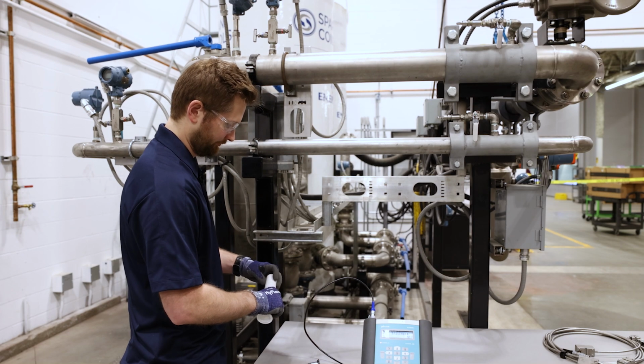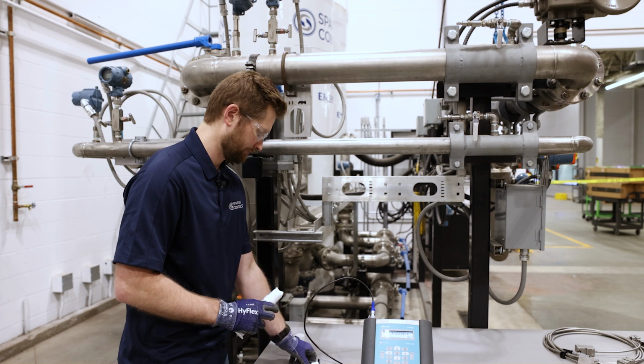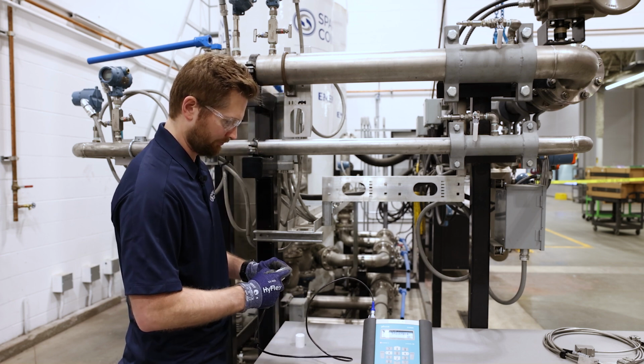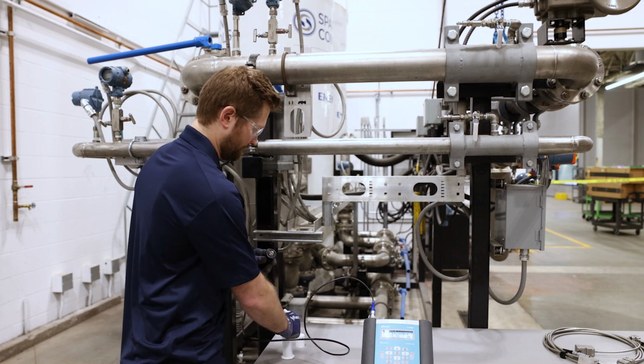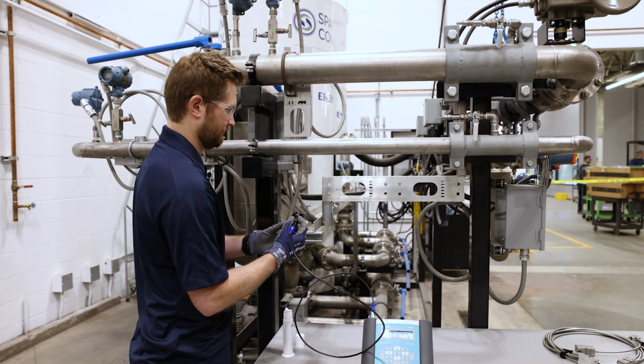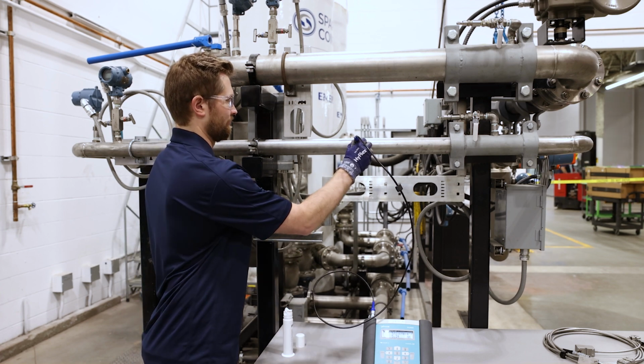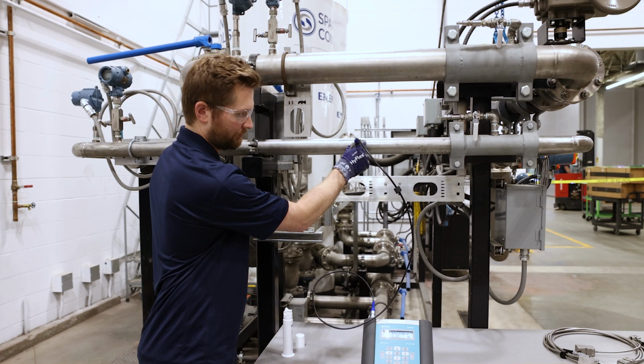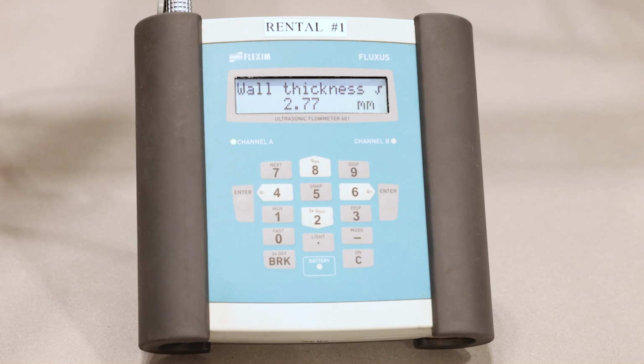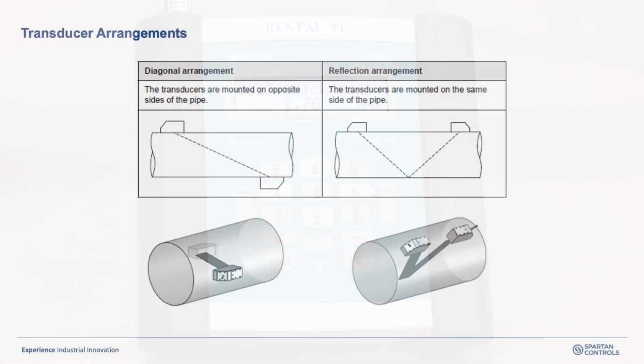We will want to apply some acoustic coupling to the probe and place it perpendicular to the pipe. Once the light goes green, this will show you the measured wall thickness. Our spec calls for a wall thickness of 2.76 millimeters.